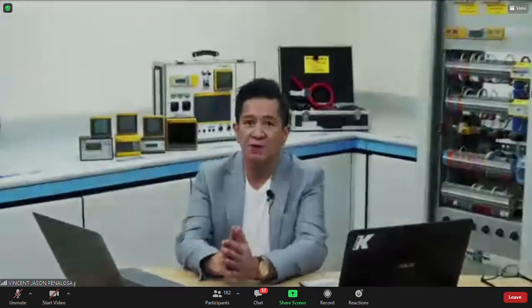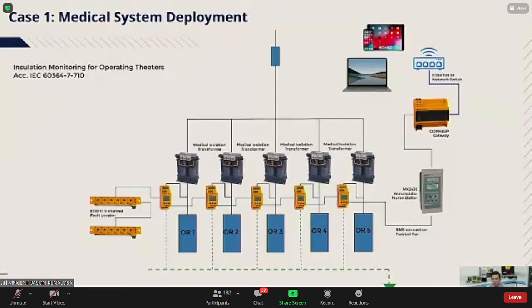Okay, so let's go now to the case studies. Here is a little bit of a case study that we've actually installed. It's 5 ORs, all of which are 10 kVA. Now, it is a case study, but in terms of compliance, it's not exactly compliant to IEC because of the annunciator, the gray one. If you can see it, the MK2430 annunciator nurse station. Now that's in the nurse station. What the IEC says is that it should be in each operating theater.